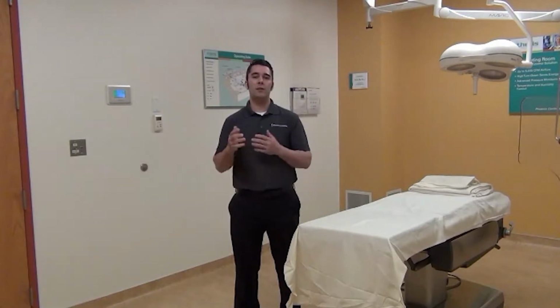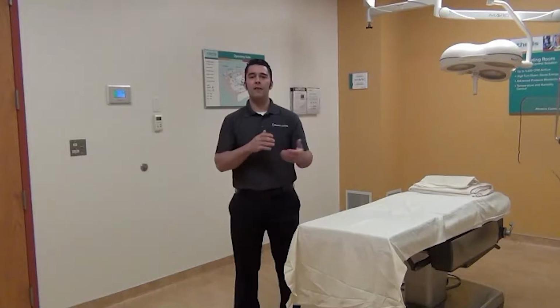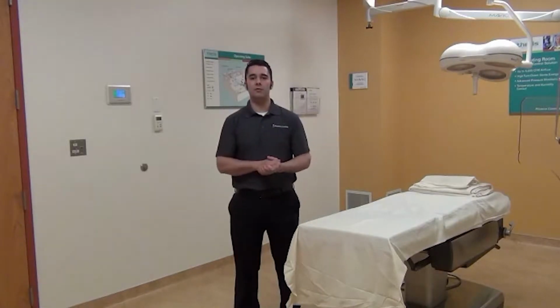So what I'm about to show you is the difference between how Phoenix Controls valves work going from occupied to unoccupied and going from about 9 air changes up to about 30 air changes. And then I'll also show you how the terminal boxes do when they're using their flow measurement techniques to hold the pressurization steady.